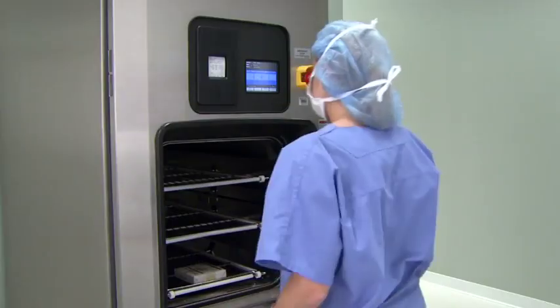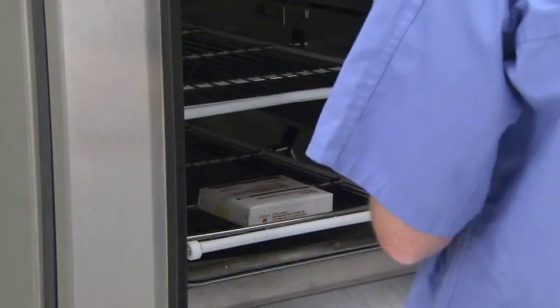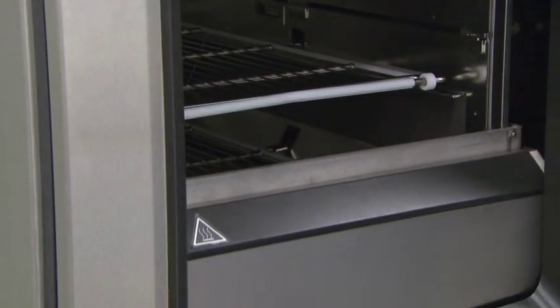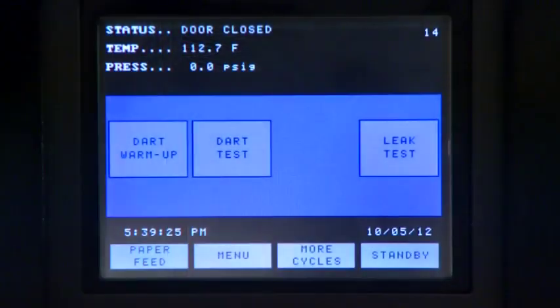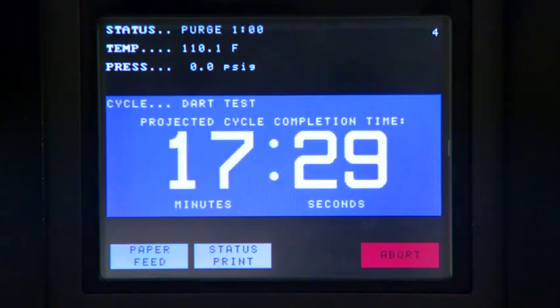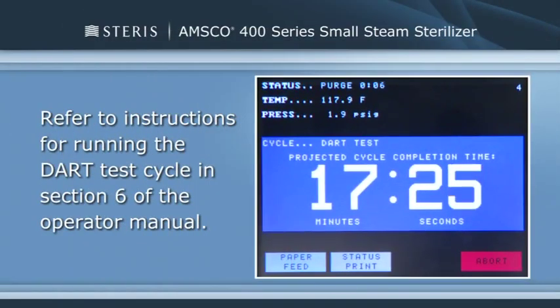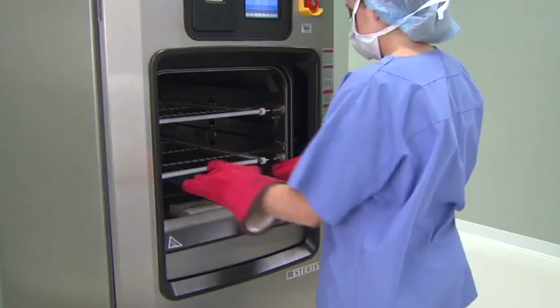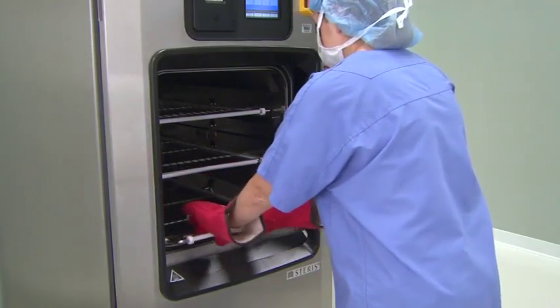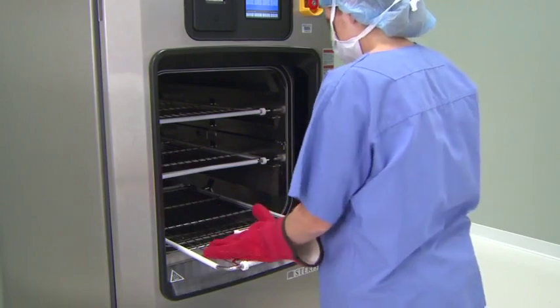Tests such as the DART or Bowie-Dick are designed to document the removal of residual air from a sample challenge load. Run a DART cycle daily before processing any loads in a sterilizer equipped with pre-vacuum cycles. The first pre-vacuum cycle of each day should be used to test the adequacy of air removal from the chamber and load, so that steam can penetrate the load. It is not a test for adequate exposure to heat in terms of time at temperature.